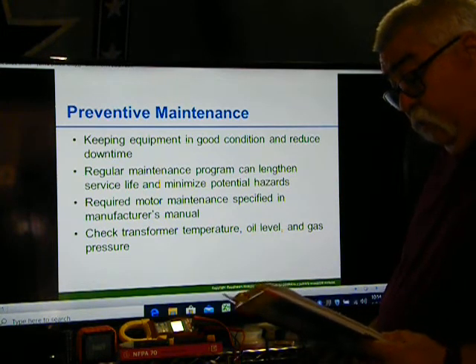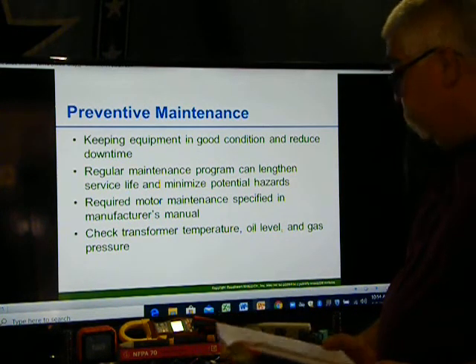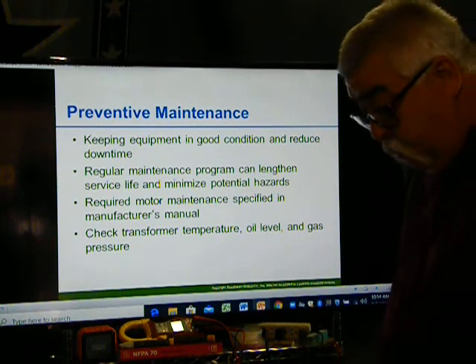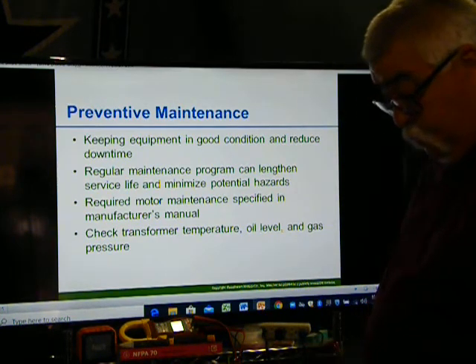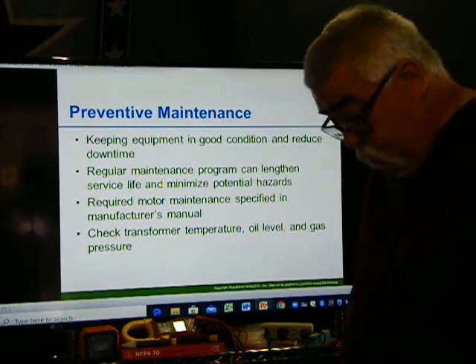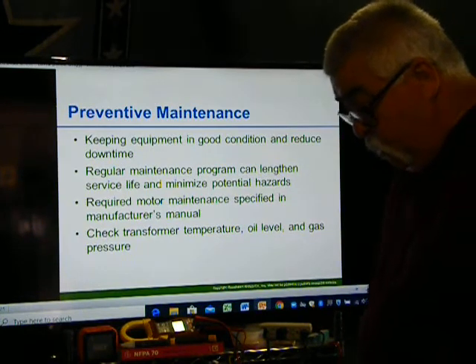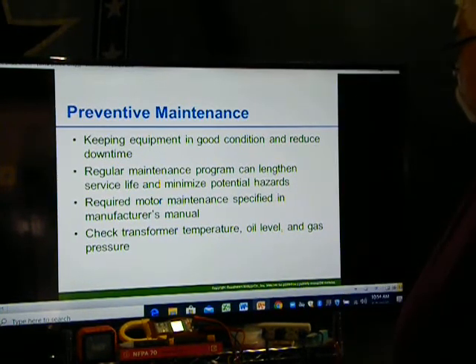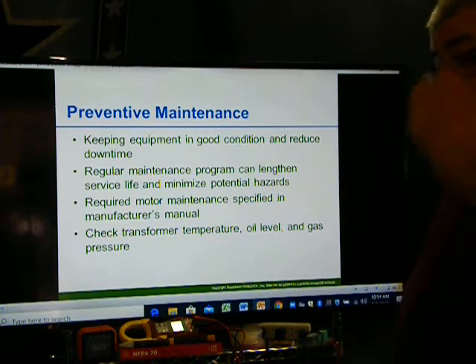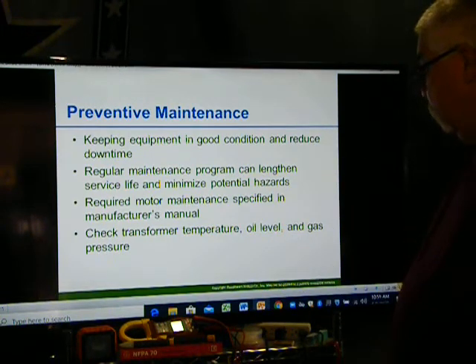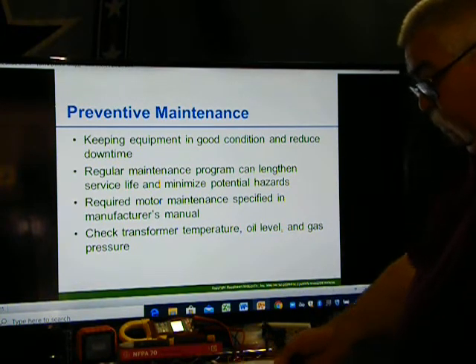As a bare minimum, the following equipment should be regularly inspected. You should check the transformers, lighting fixtures, cables, switchgear components, circuit breakers, relays, motors, and metering equipment. So check the transformer. If you have an oil-filled transformer, check the levels. Make sure if it's pressurized.